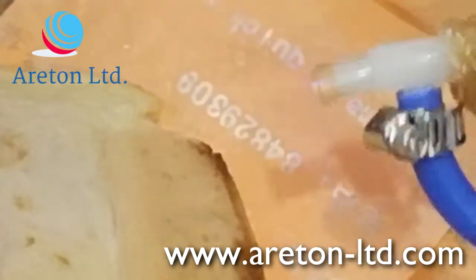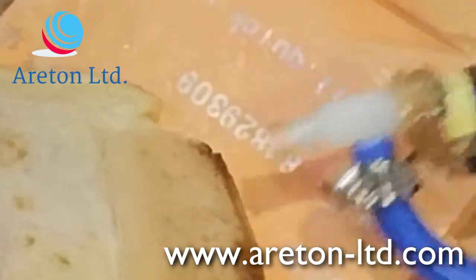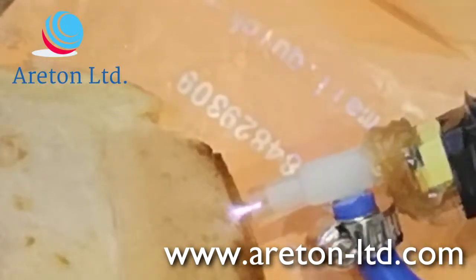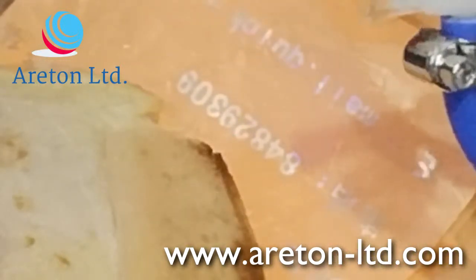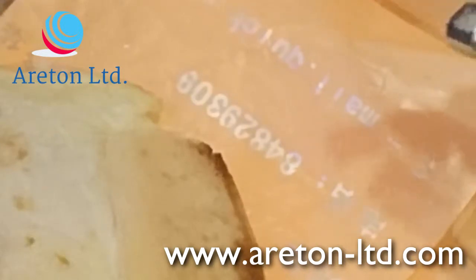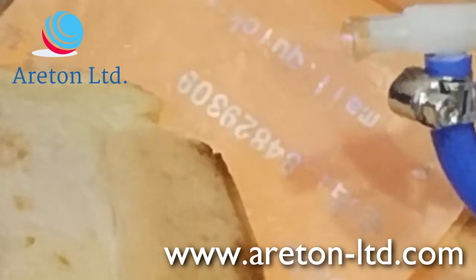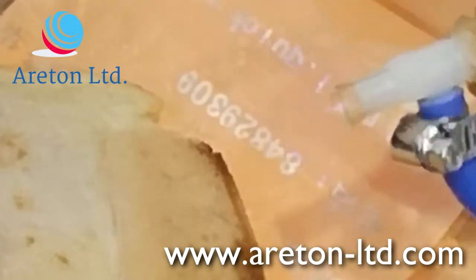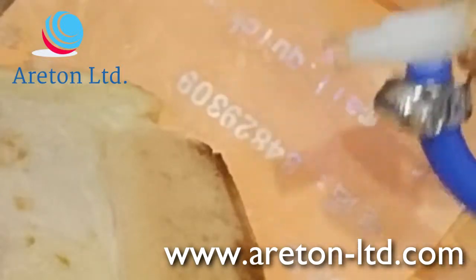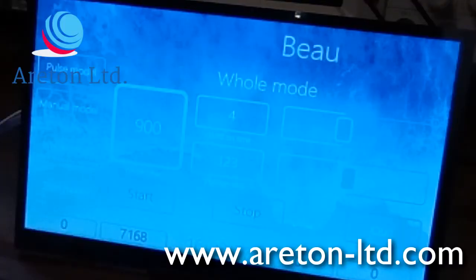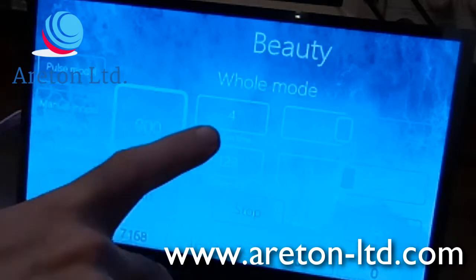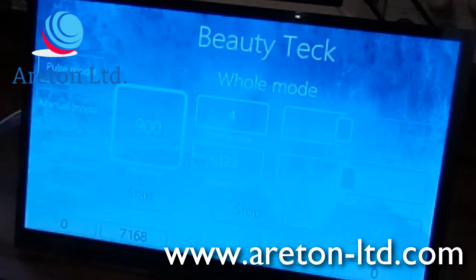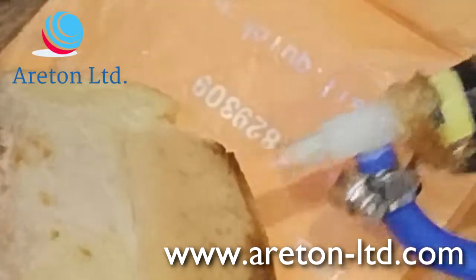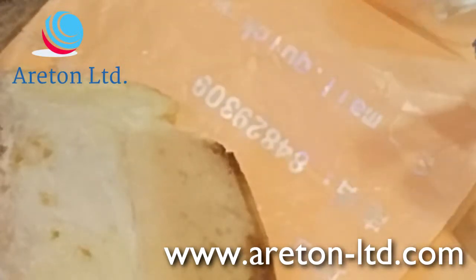A tiny bit, and it's still on. Then another tiny bit, and it's still on. So it's set up almost properly, but there are some settings that we've got to change on this device in order to detect the arc properly. But look at this. The wait time is 4 seconds, and the hold time is 900 milliseconds. So I'm going to show you some bursts, to see how many we can actually produce.